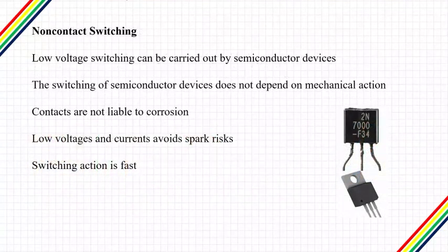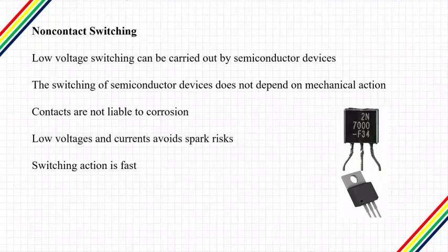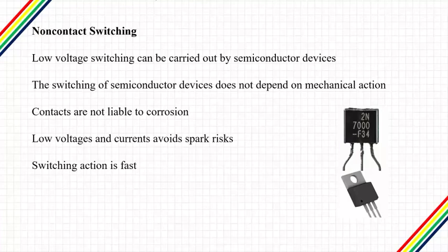Non-contact switches do not use a mechanical system. These are applicable for low voltage switching and can be carried out by semiconductor devices such as BJTs, FETs, or thyristors. The switching of semiconductor devices does not depend on mechanical action. The main advantages of this type of switch are that it can be used in hazardous environments because the switch contacts are not exposed to the environment, so corrosion and other material degradation are not possible.